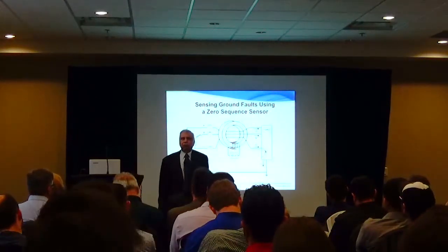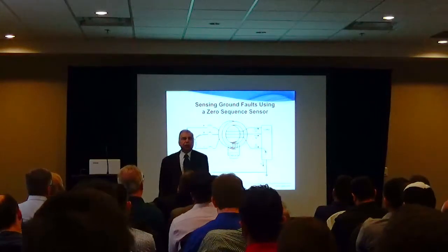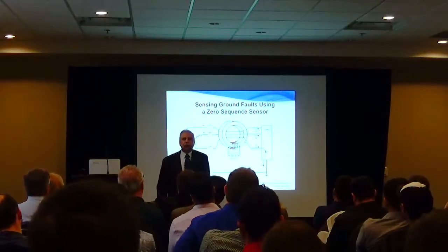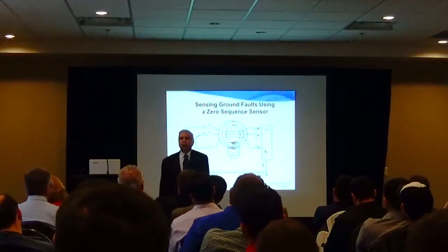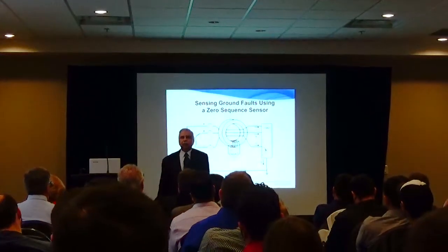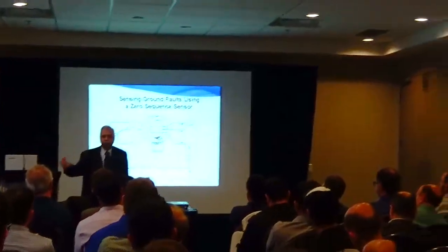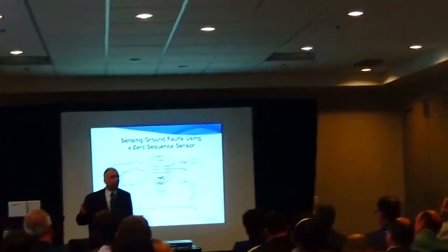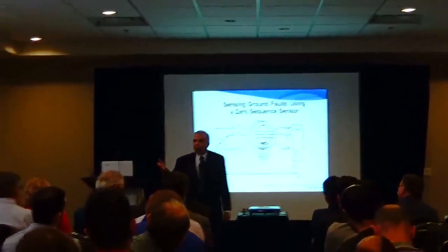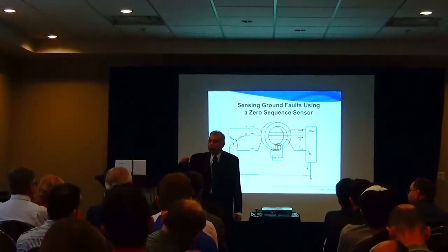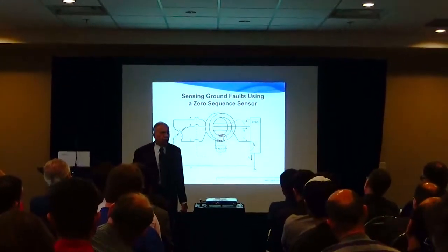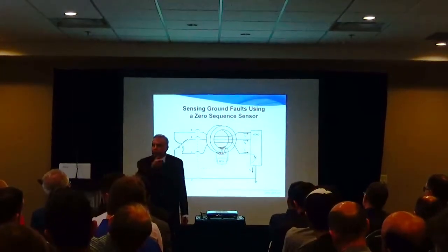Not a traditional current transformer. In a traditional current transformer, you may have, let's say, a 50 to 5 CT or 100 to 5 CT. You residually connect the secondary currents, and then the relay would be calibrated for secondary current in terms of 5 amperes, and set for something close to more than 10% of the reading. So you can adjust the relay to 500 milliamps secondary current, and then apply the turns ratio to see what the primary current detection level is.